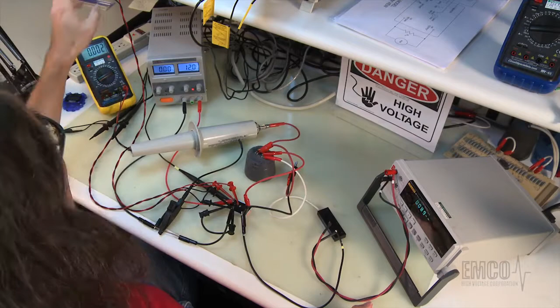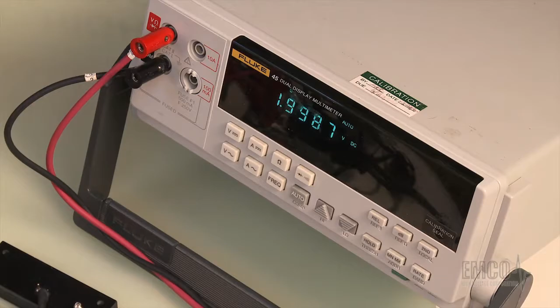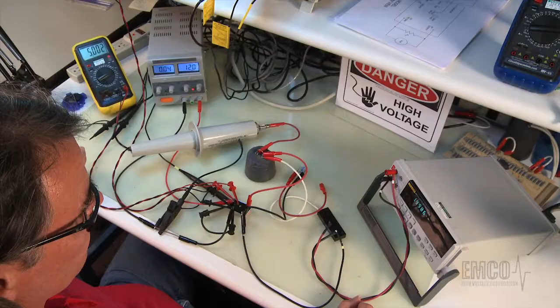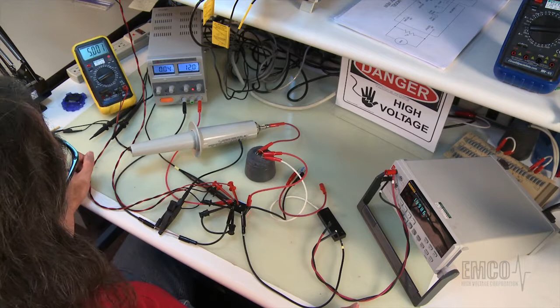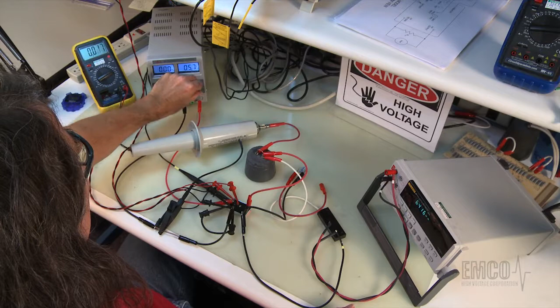So now with the load applied, we can go ahead and turn on the programming voltage again, and we can see with the load applied, we return to approximately the same nominal output voltage within the regulation spec of the CA20P. So it shows the output is very tightly regulated. So of course, before you leave the setup, you probably want to turn off the output voltage to return the equipment to a safe condition. So I'll go ahead and turn that off and just set the programming voltage to 0, and of course drop our input voltage back down to 0 with the conclusion of the test. So essentially that's it for the demonstration.